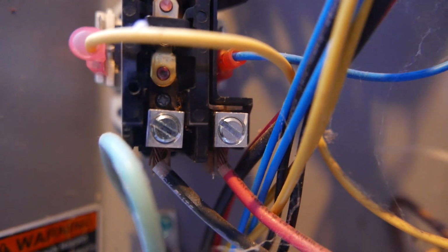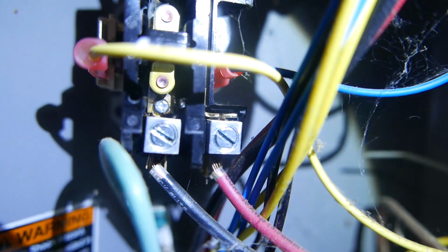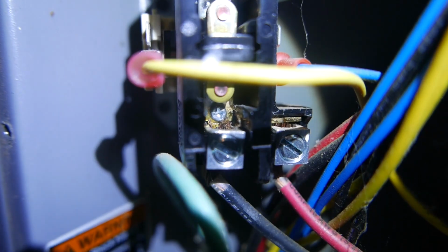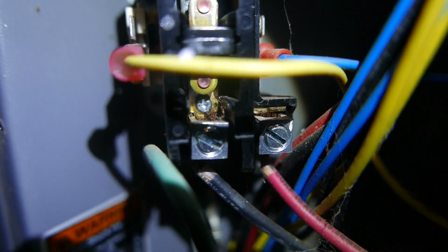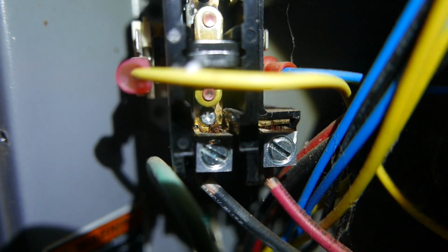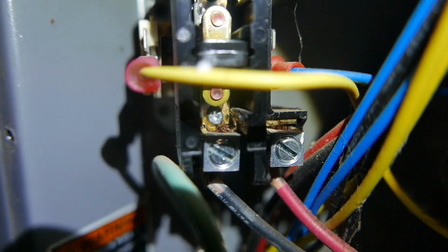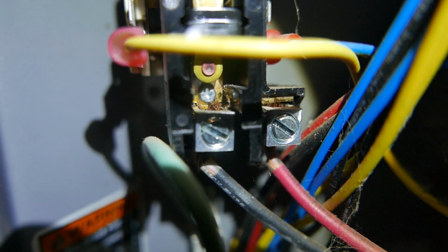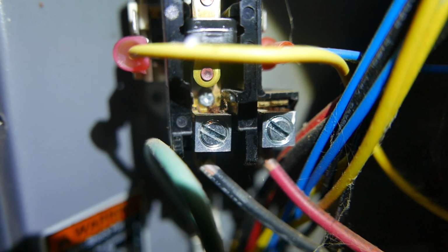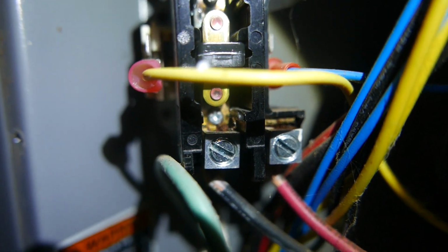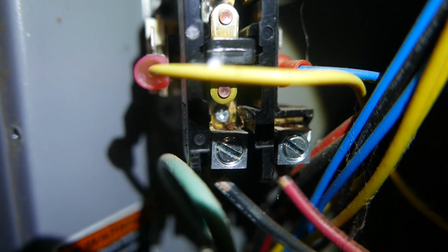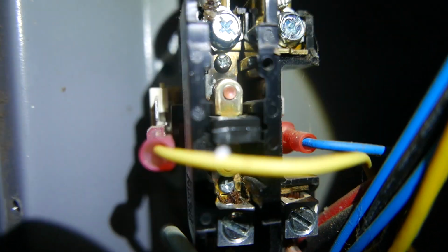So I found out what caused this issue. I don't know if you can see, but there's a load of ants right there - I can count at least 4 or 5 ants. Ants are attracted to electricity, or sometimes they just walk in the path of electricity. They happened to be at the wrong place at the wrong time and caused this contactor to clog up. These ants are what caused this contactor to fail.